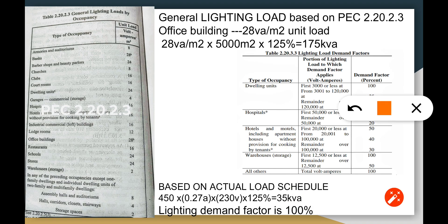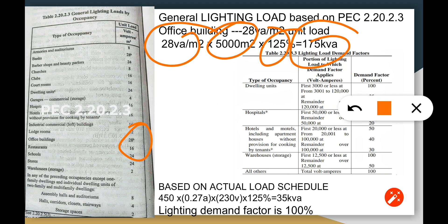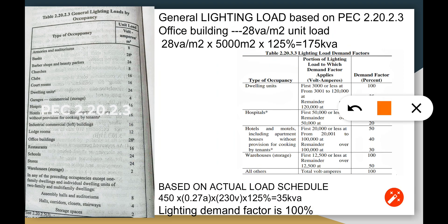According to general lighting loads, based on the office building we have 28 VA per square meter multiplied by the square area with a continuous load of 125 percent, and we shall get 175 kVA based on the PEC code. Based on the actual load schedule, we shall have 450 pieces of lighting load times 0.27, which is 230 for the ballast amperes, times 125 percent, and we get 35 kVA.